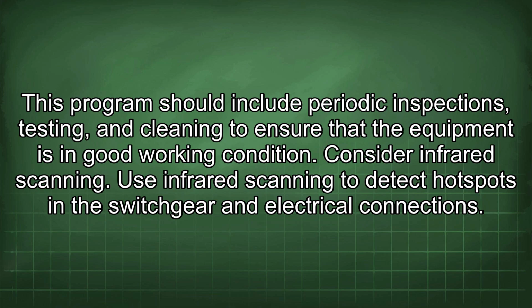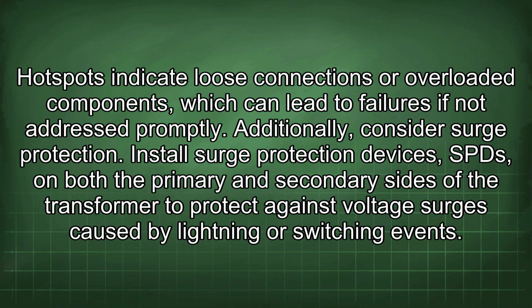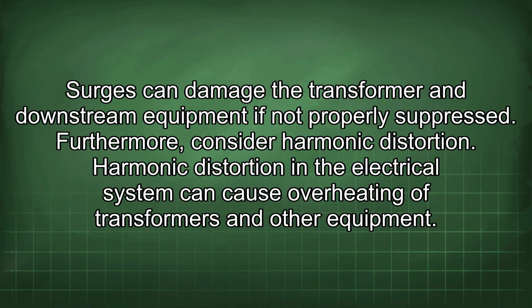Consider infrared scanning. Use infrared scanning to detect hotspots in the switchgear and electrical connections. Hotspots indicate loose connections or overloaded components, which can lead to failures if not addressed promptly. Additionally, consider surge protection. Install surge protection devices, SPDs, on both the primary and secondary sides of the transformer to protect against voltage surges caused by lightning or switching events. Surges can damage the transformer and downstream equipment if not properly suppressed.